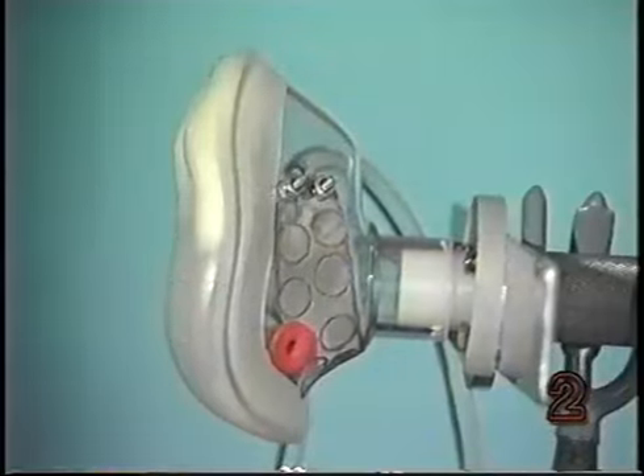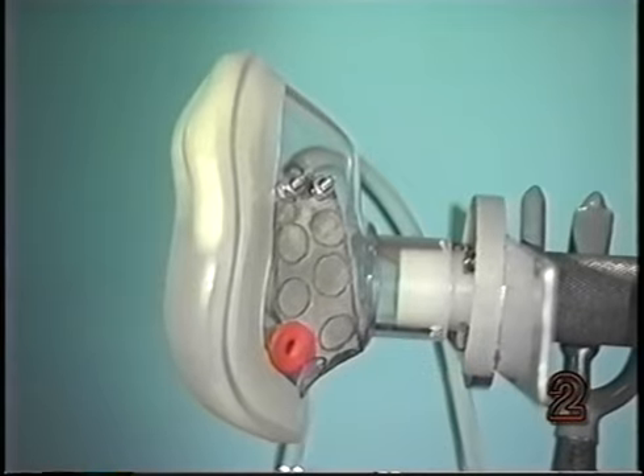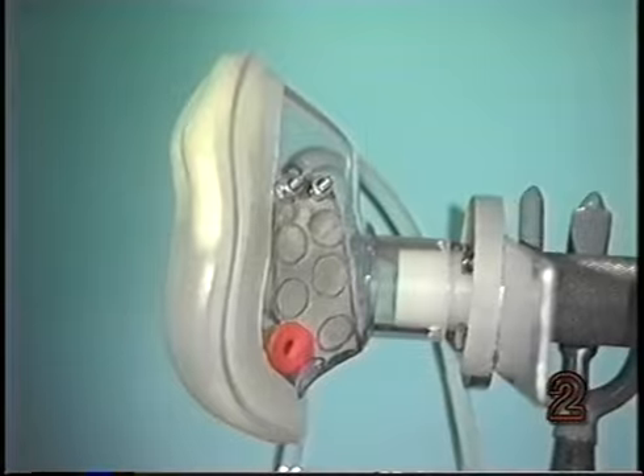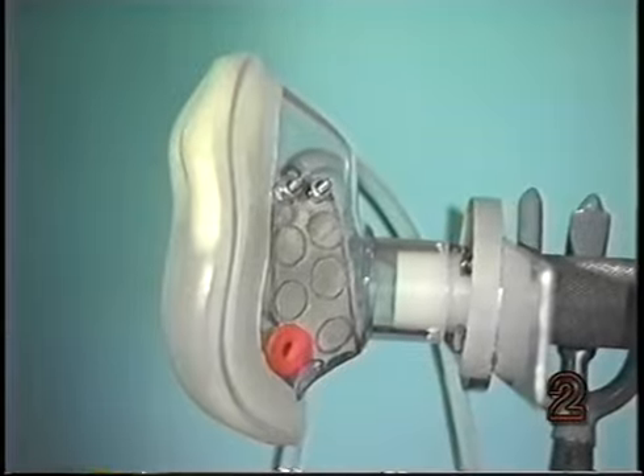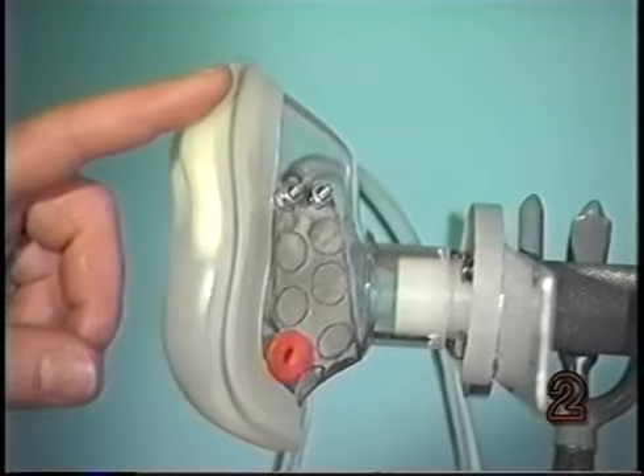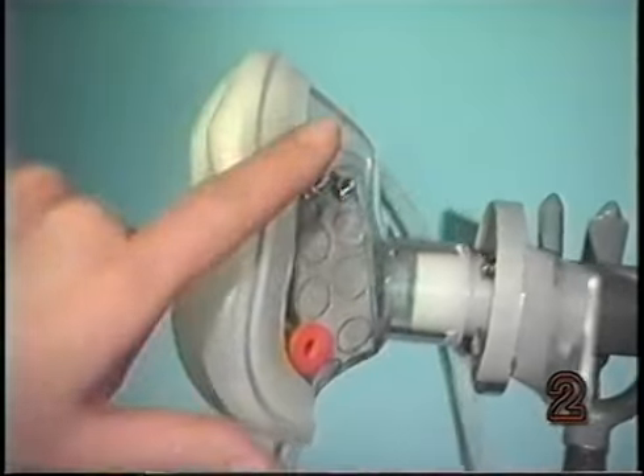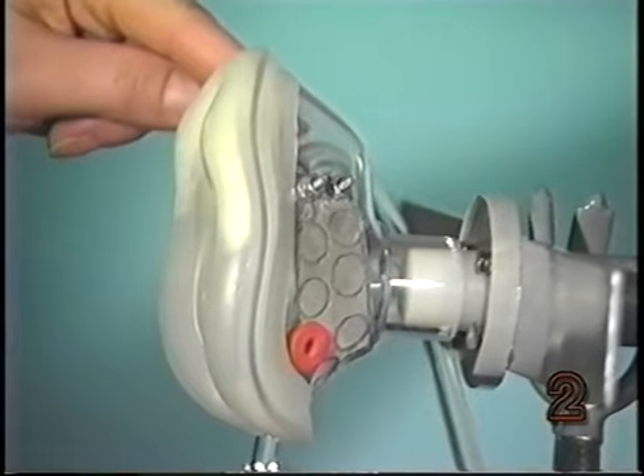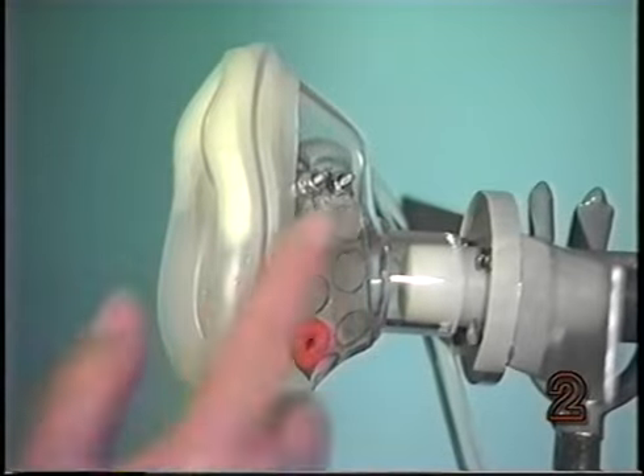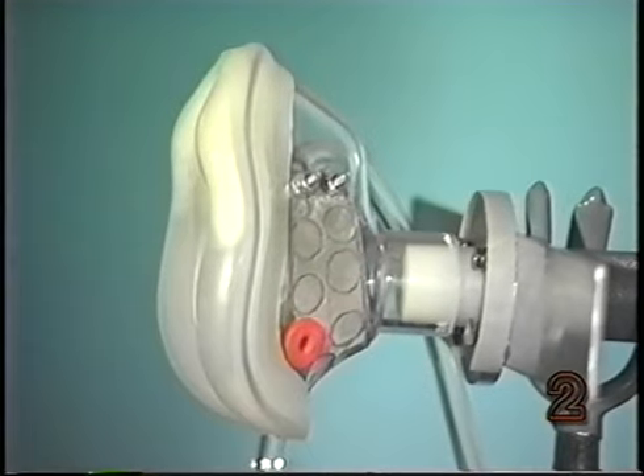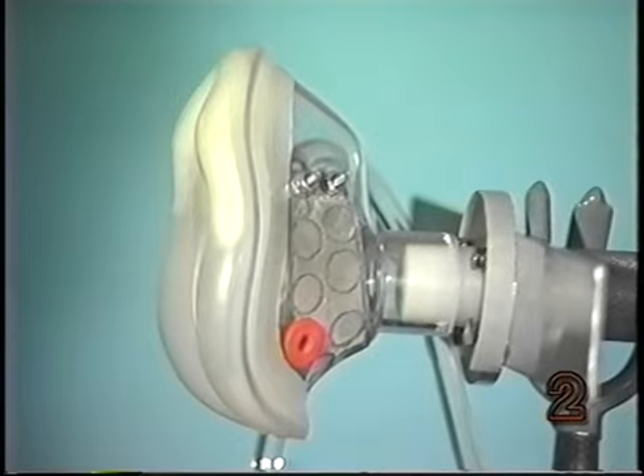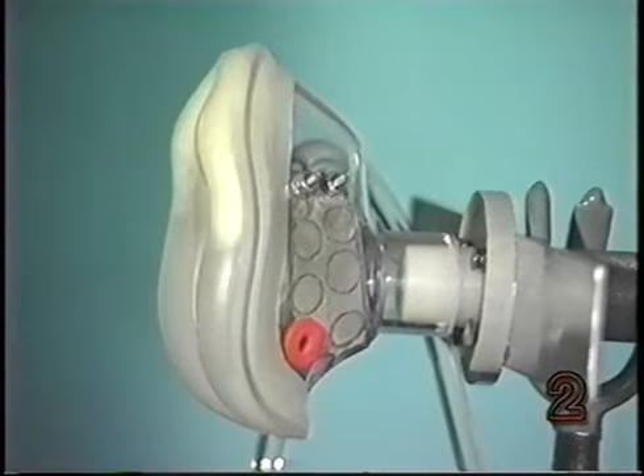The first device is called a pneumotachograph mask and is used for sensing airflow. This particular mask design can be described as being circumferentially vented and was developed by Martin Rothenberg at Syracuse University. As you can see, it's made from a standard respiratory face mask which has a series of holes punched around the circumference of the mask. The holes are covered by a fine wire mesh, and that presents a slight resistance to the flow of air through the mask. The resistance causes a pressure differential which is proportional to the airflow through the mask.